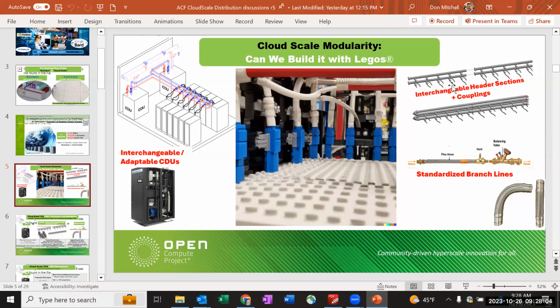I'd expect the same thing with the picture in the top left. If you ran CDUs out to facility water, your IT-side coolant could be 100 micron filtered in the CDUs, and as long as none of the servers in the cabinets were microchannel cold plates, you'd be fat and happy and off you go. But if somebody at some point switches to a microchannel cold plate server, you're screwed, you've got to change your filtering.